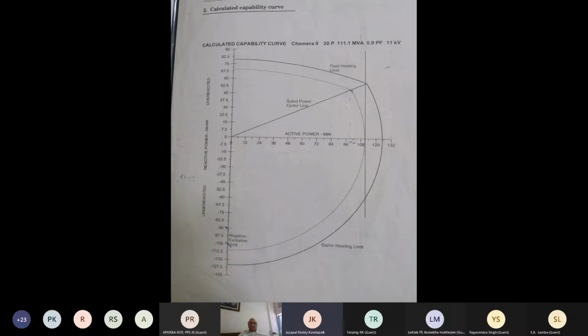Okay, sir, under excitation, as per my knowledge, means the field current is already less than the required flux, no, sir? So how is stator heating a limit? No, field current is not the issue. See, air gap flux will remain as required, but partly the air gap flux is given by the reactive power taken from the grid in the under-excited mode. So the air gap flux is a mixture of flux density produced by the field winding and the excitation drawn from the grid. That's why there is overheating, because you are drawing excitation from the grid. So there is overheating of the teeth in the end region, and this limitation comes out of that.